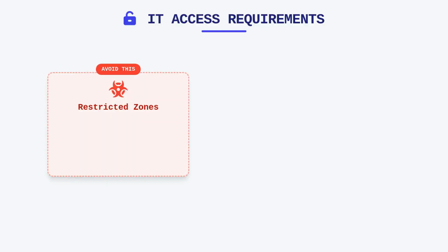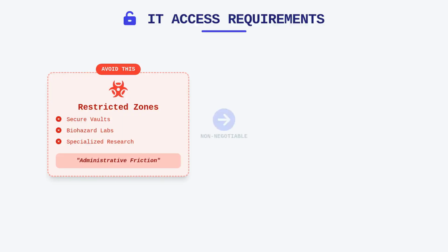Perhaps most importantly, you must enforce the requirement for 24-hour unescorted access for authorized IT personnel. The placement of a telecommunications room inside a restricted zone, such as a secure vault, a biohazard lab, or a specialized research area, introduces unnecessary administrative friction that can prevent timely emergency maintenance. When a service outage occurs in the middle of the night, your team should not need to petition security clearance from another department just to access the hardware responsible for network availability.